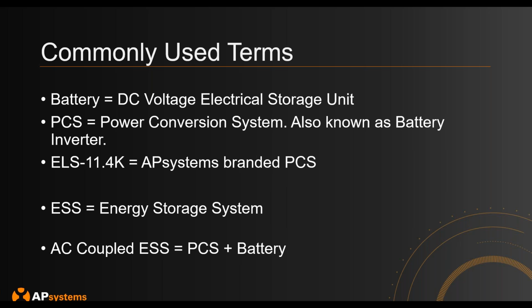Another term I'll use is PCS, which stands for Power Conversion System, not to be confused with power control system. Another name for the PCS is a battery inverter. It's basically a bidirectional AC-DC inverter that takes the DC battery and converts it to AC voltage so it can interface with the grid. It's almost like a microinverter, which is the AC-DC linkage between the DC solar panel and the AC grid. It's very similar, but the main difference is the PCS, or battery inverter, is bidirectional, so it can not only output power but also input power to the battery.